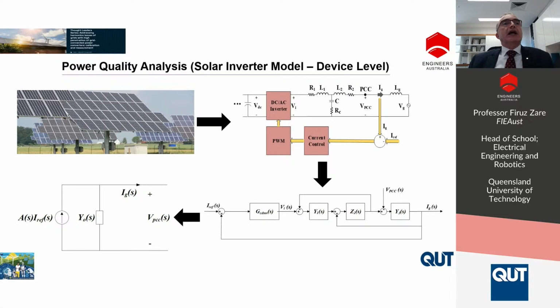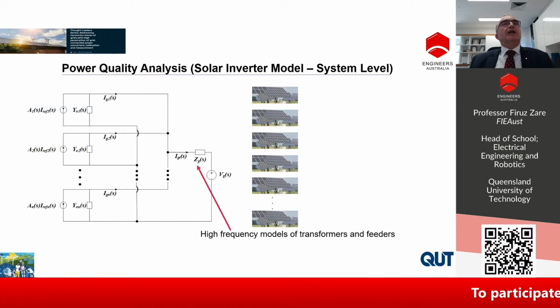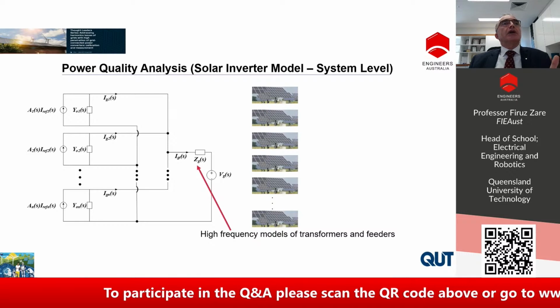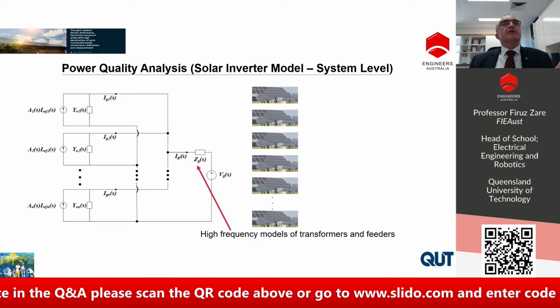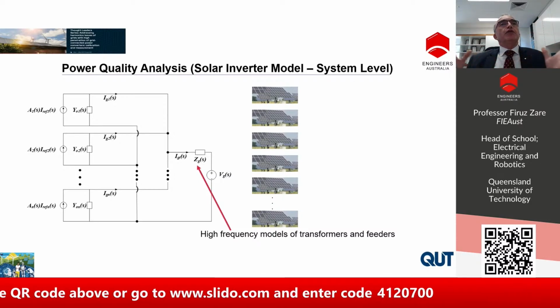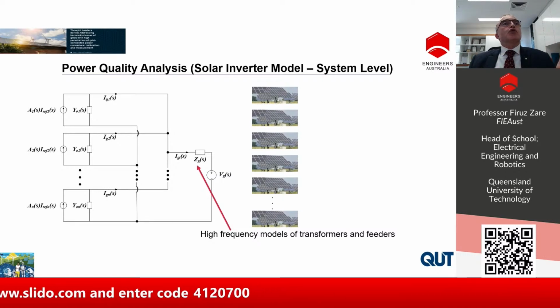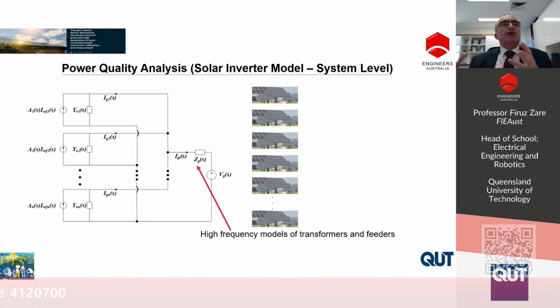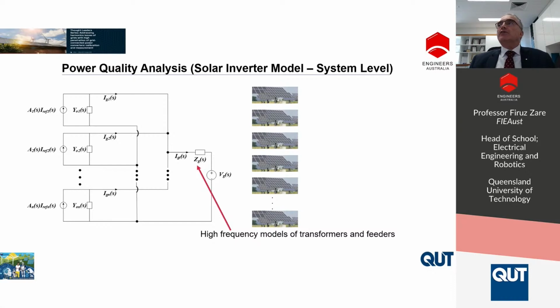And those resonances in a solar farm can interact with other inverters. This technology is similar to the battery charger, which means that all battery chargers based on an active front-end converter have some resonances. With multiple inverters connected together, when all have similar technology, we don't have any problem in terms of resonances because they are more or less the same technology. But in a residential area, where we have a high number of different solar inverters, we expect significant interaction between some of them if the switching frequency of one is tuned to the impedance of another inverter. That's why we expect some interaction in residential or grid-connected inverters.